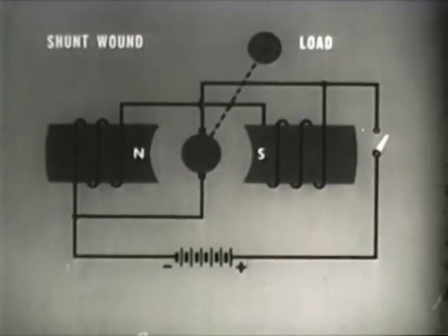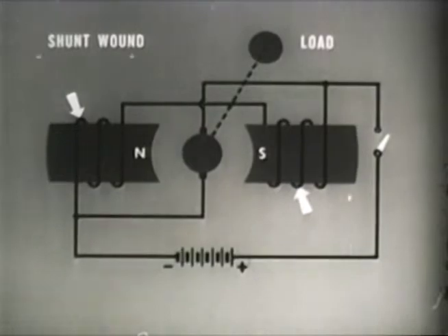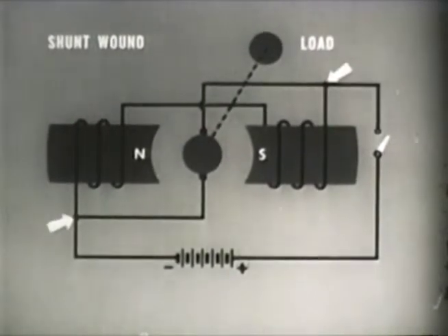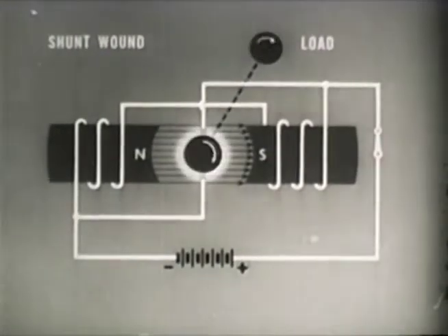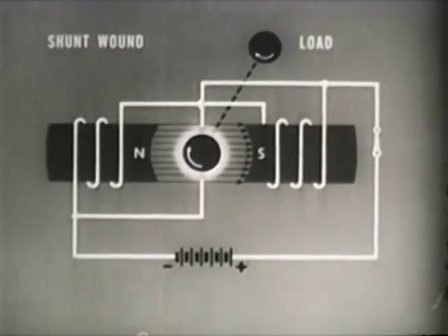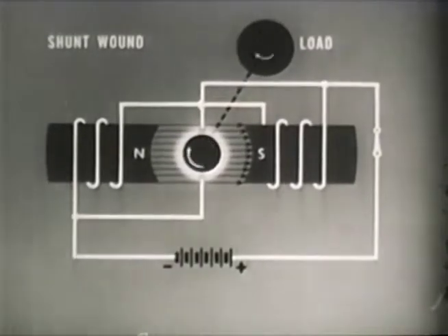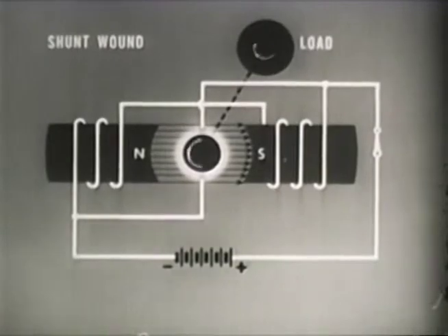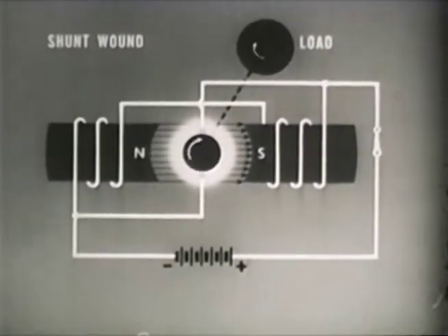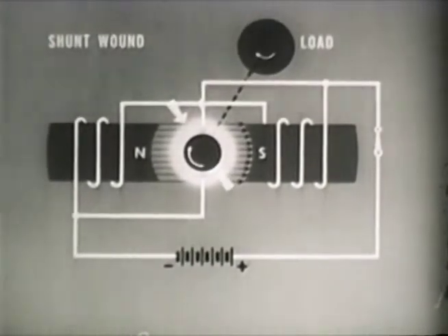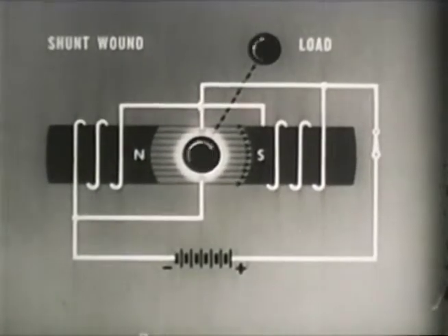The shunt wound motor has less starting torque, but it is less dependent on load for speed control. In the shunt wound motor, the field coils are connected in parallel directly across the DC input terminals. The starting torque is not as great as in the series motor, since field strength is not affected by armature current. The speed of a shunt motor is fairly constant under conditions of changing load. As more load is applied, the speed of the armature decreases, which decreases the CEMF and increases the current input. The increase in current input boosts the coupling between the field and armature and increases the torque, causing the motor to resume approximate running speed. A sudden reduction in load will not damage the motor because the field current is independent of rotor current in the shunt wound motor.